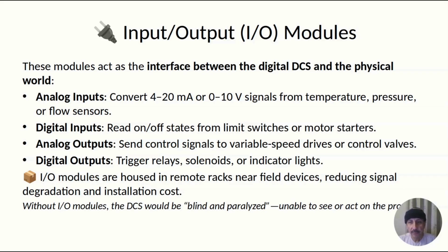Now here's a key design point. These I/O modules aren't crammed into the main control room. Instead, they are installed in remote I/O racks located close to the actual equipment, often in weatherproof enclosures right on the production floor or along pipe racks. Why does this matter? Two big reasons. Signal integrity. Analog signals degrade over long cable runs. By placing I/O near the source, we can minimize the noise, interference, and the voltage drop, ensuring accurate measures.